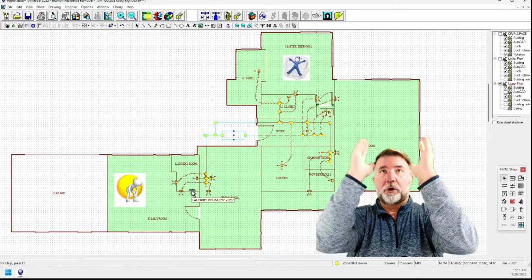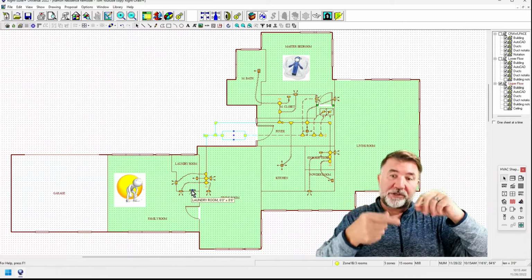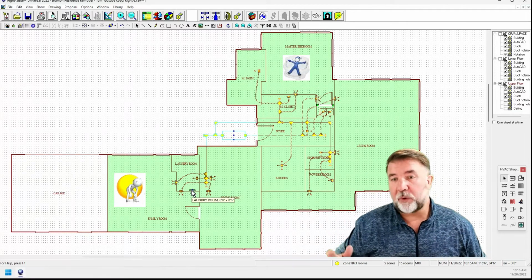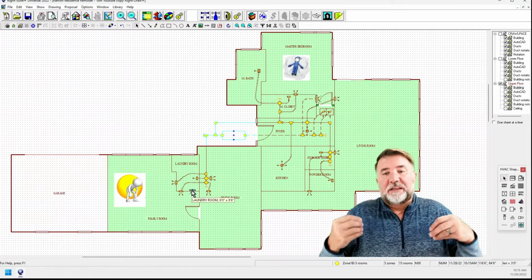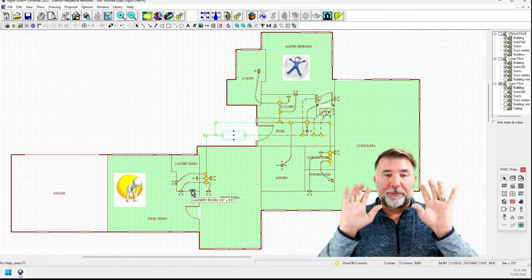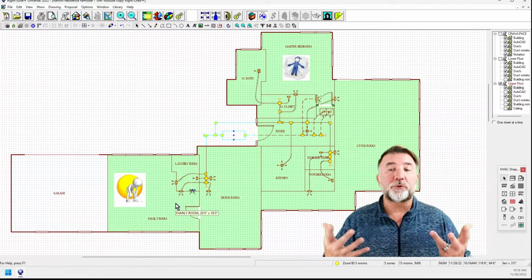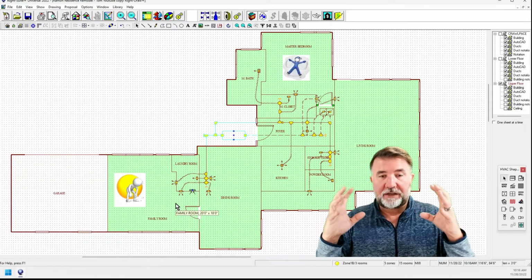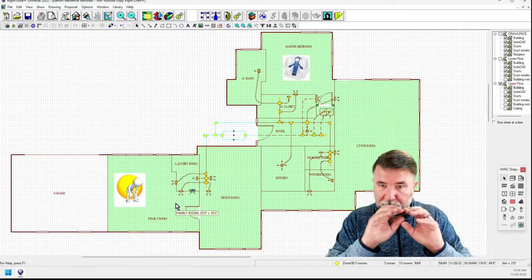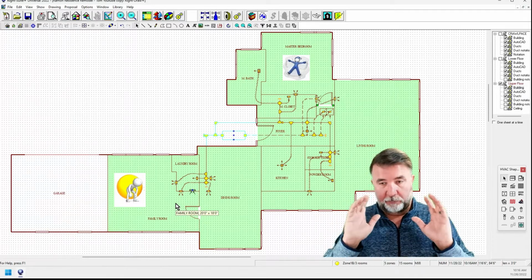If you look above the doors, you'll see that there's a grill. And if you go on the other side, you'll see another grill. So you see two grills and the air is passing through those grills. That's a transfer grill, and that's basically like an undercut in the door, but you're making it a little bit bigger. So what's happening is the air comes out and you're blowing air into an enclosed room. So you're pressurizing it. And the more air you put in there, the greater the pressure of the room, and you're going to push that air out.